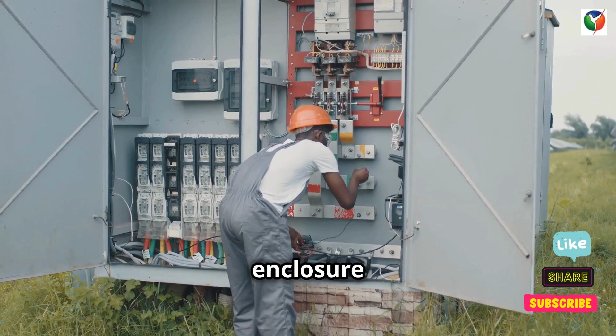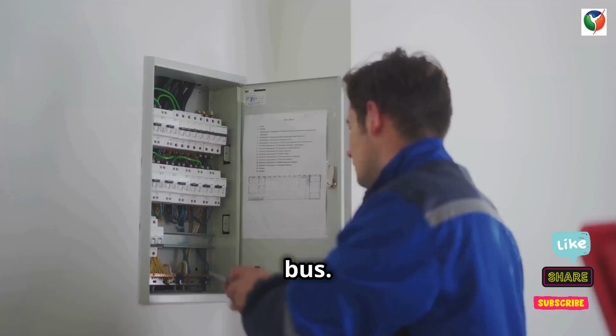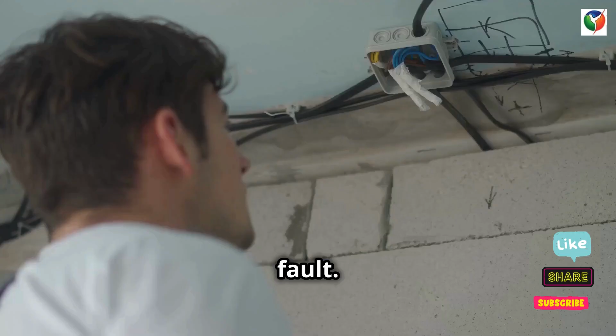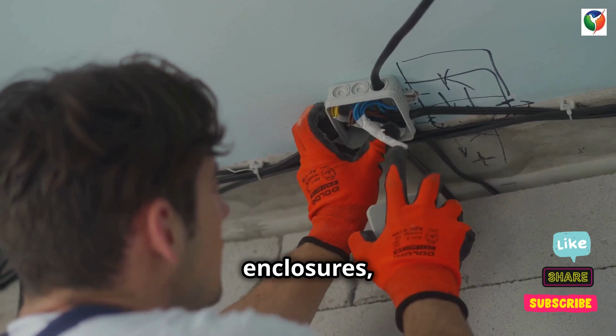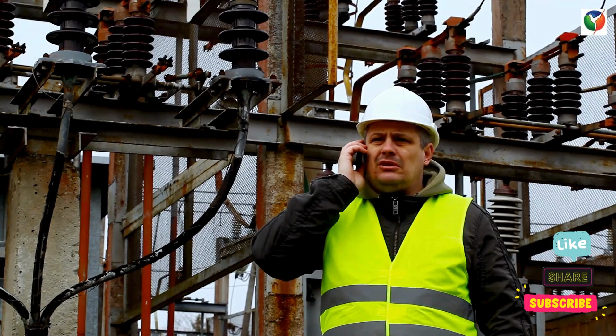Inside the same electrical panel, the metal enclosure is bonded to the ground bus. This ensures that the panel's metal parts do not become energized to a dangerous voltage during a fault. It also ensures that all metal enclosures, like conduit and junction boxes, are at the same potential, preventing shock.